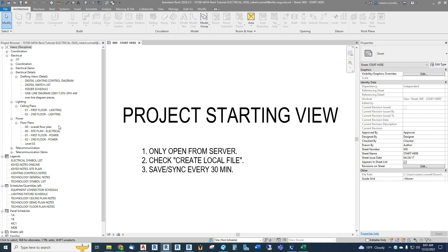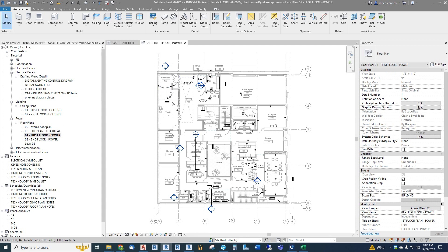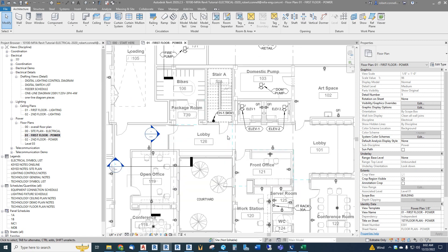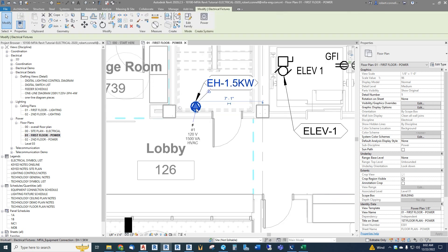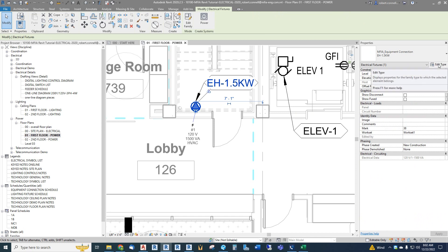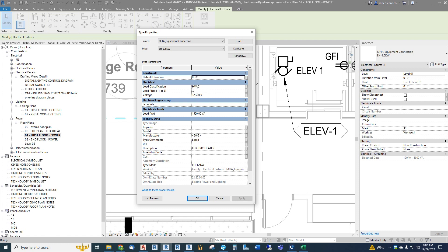We looked at the equipment schedule when we inserted the equipment, but we'll review that again. Let's go to our power plan, first floor. We left off with the receptacle circuit, and now we need to circuit up some equipment. Let's start with an electric heater — our EH 1.5 kW. As a review, let's look at the parameters for this type. Each piece of equipment that is different we labeled with different types. This one is the 1.5 kW, set up as a 120-volt single-phase connection with an HVAC load classification.